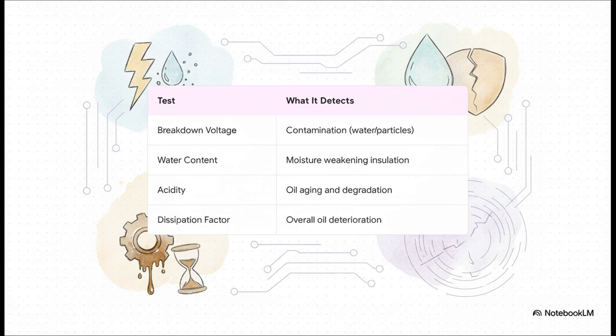I mean, engineers run a whole panel of tests on this oil blood. They'll check its breakdown voltage to look for contamination. They measure water content because moisture is the mortal enemy of insulation. They test for acidity, which tells them the oil is getting old, and they measure something called the dissipation factor to check for overall decay. It is a truly comprehensive physical.